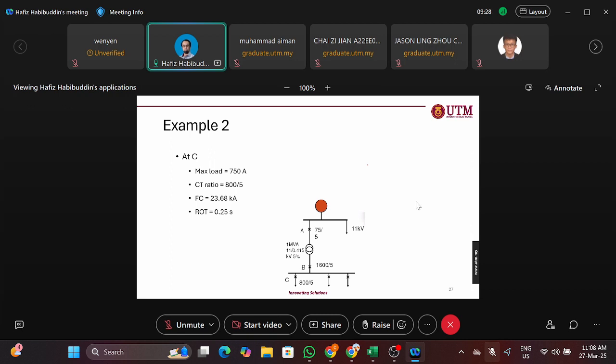First, of course, is the current setting. These are the information that we have. The waiting time is given. So from the equation of the plug setting, it should be greater than 93.75. So you take the closest one. Let's just assume the closest one is 100. Of course, it should be provided in detail in the example.